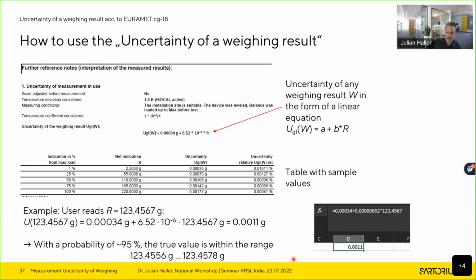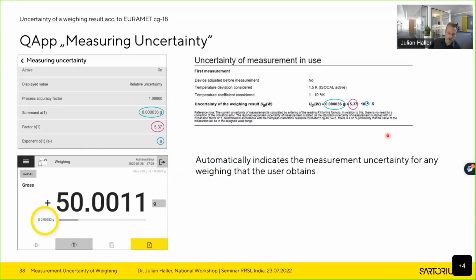So that is how this can be used to calculate the uncertainty of any weighing result, in the comfortable situation that a calibration lab might make the uncertainty determination for you. And even more comfortable, our premium balances do have internal functions. So for example, if you have this on your calibration certificate, this is what it would look like. You can simply enter these values into a respective Q app called measuring uncertainty. You have to enter all these three parts. And then you can configure this app to show you, and also in printing it will be given, the measurement uncertainty for any weighing result.